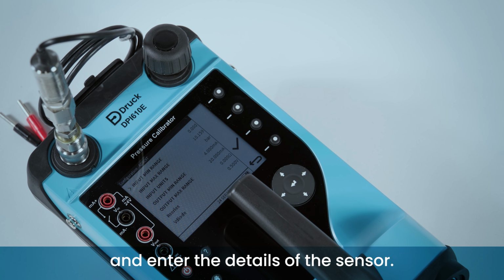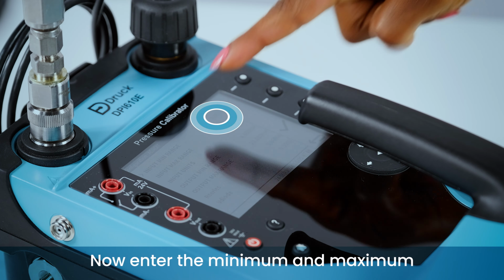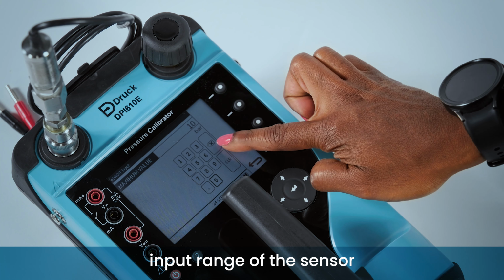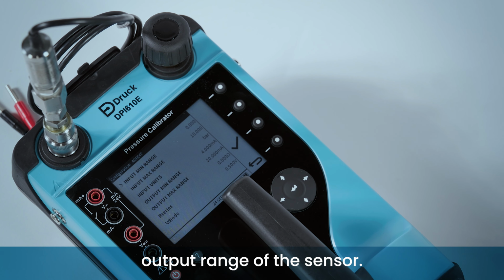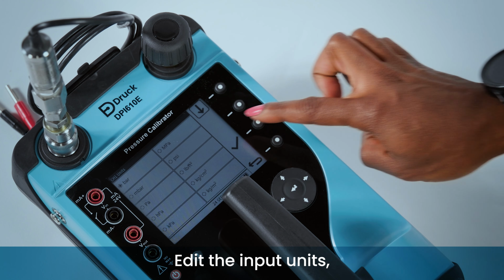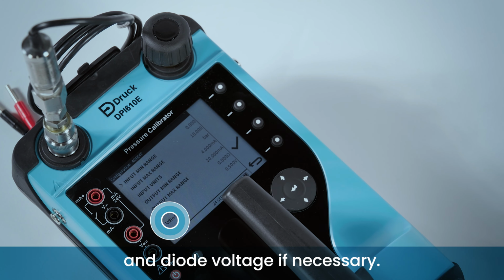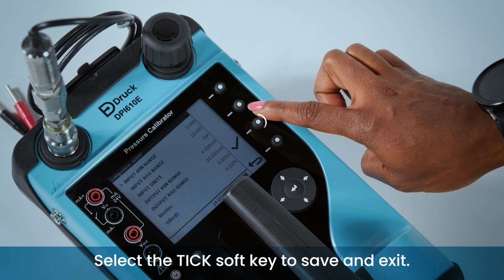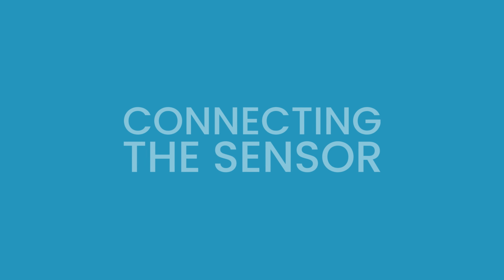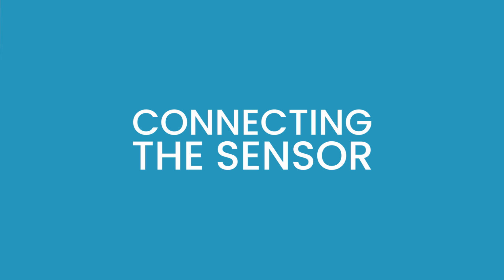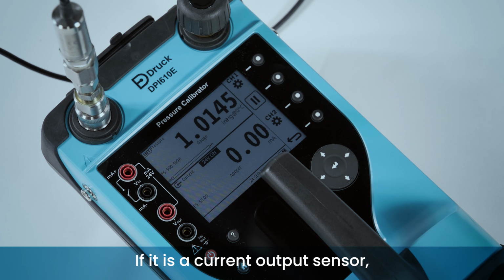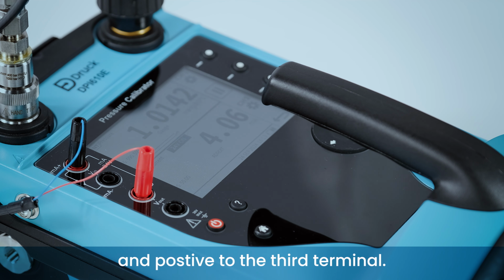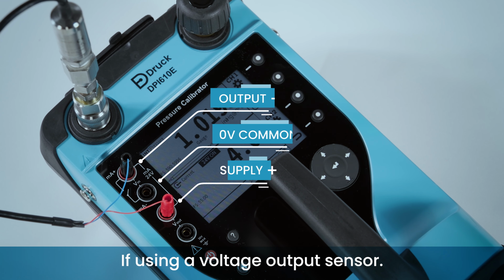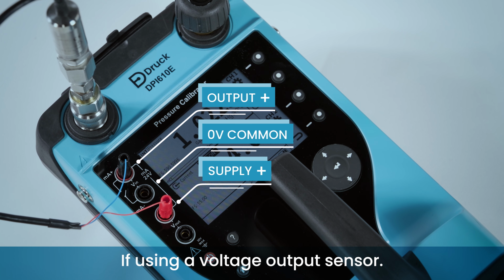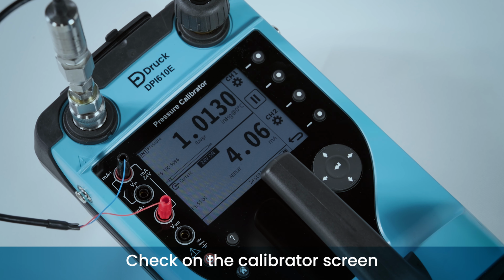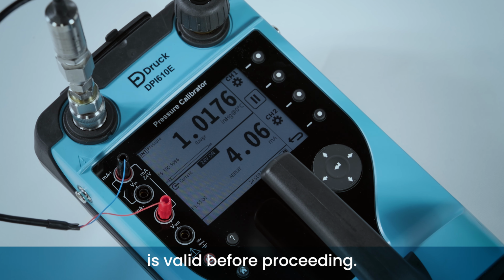Select this and enter the details of the sensor. Now enter the minimum and maximum input range of the sensor and the minimum and maximum output range of the sensor. Edit the input units, series resistance, and diode voltage if necessary. Select the tick soft key to save and exit. If it is a current output sensor, connect the negative to the top terminal and positive to the third terminal. Check on the calibrator screen to make sure the electrical reading is valid before proceeding.